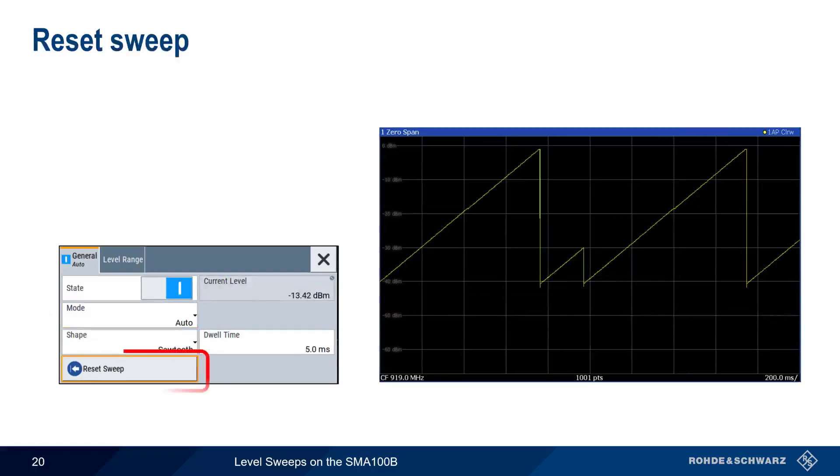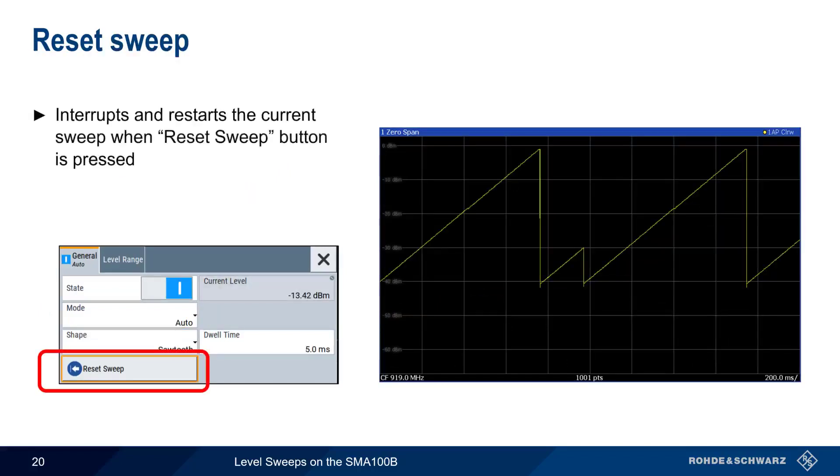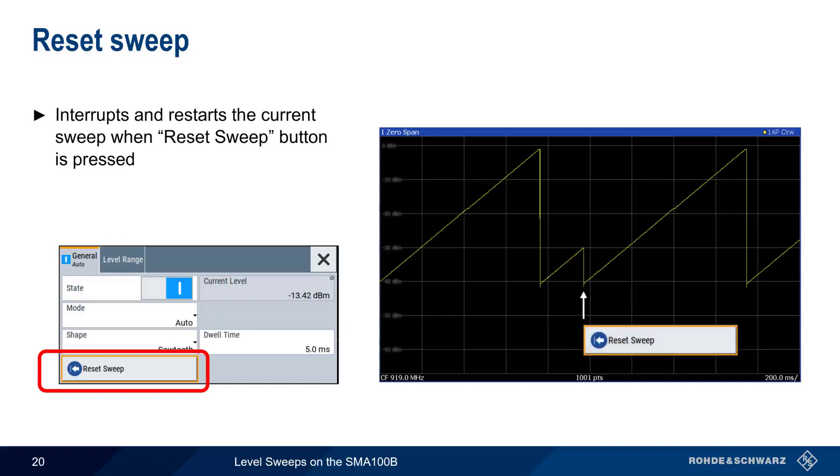Another useful function is Reset Sweep, which interrupts and restarts the current sweep. For example, by pressing the Reset Sweep button, this sawtooth-shaped level sweep was immediately restarted.